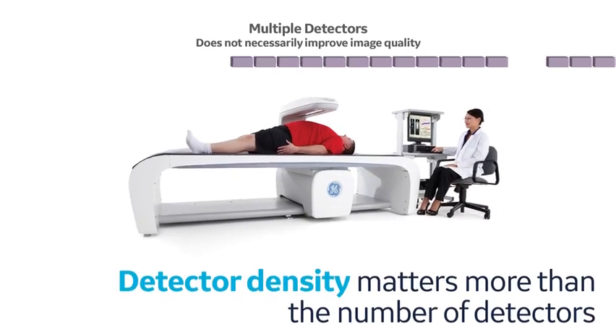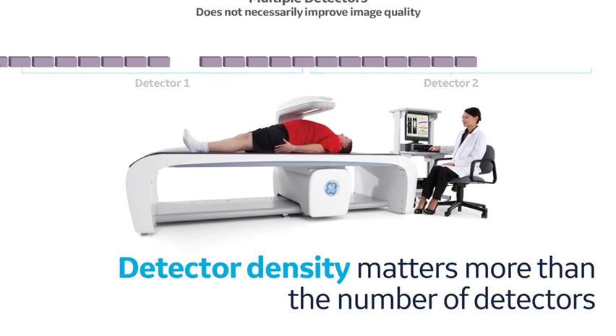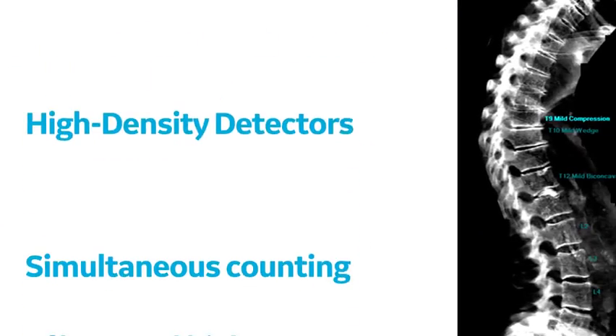As opposed to other DEXA systems, increasing the number of detectors does not necessarily improve image quality unless it is accompanied by a higher density of cells in the crystal. Also, scanning too quickly or with insufficient x-ray flux on a thick patient will degrade image quality by starving each cell of x-rays.